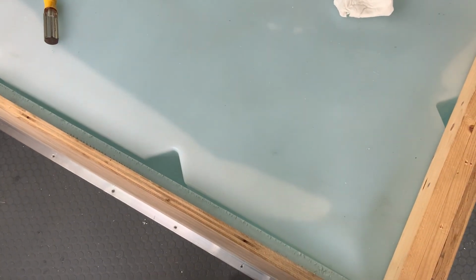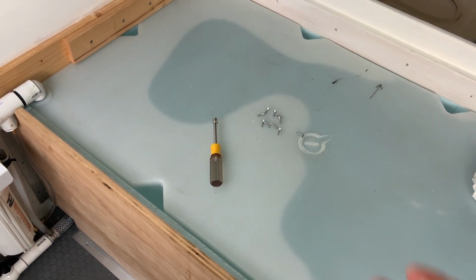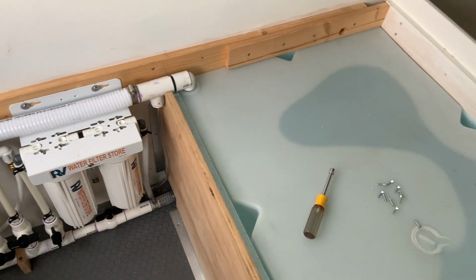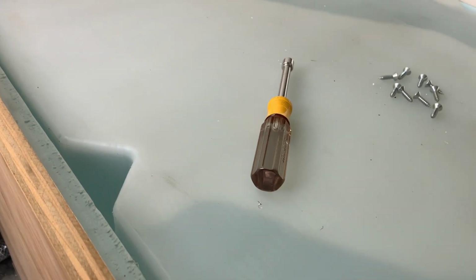I want to fill it until it starts flowing out, and I want to see how the tank responds to the extra pressure. Because there's going to be more pressure once it gets completely full and the water starts getting pushed out the vent. And I want to know that I don't have to worry about it. See, this is already floating right here now.